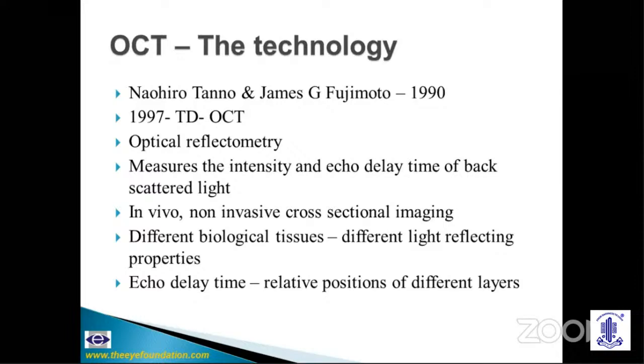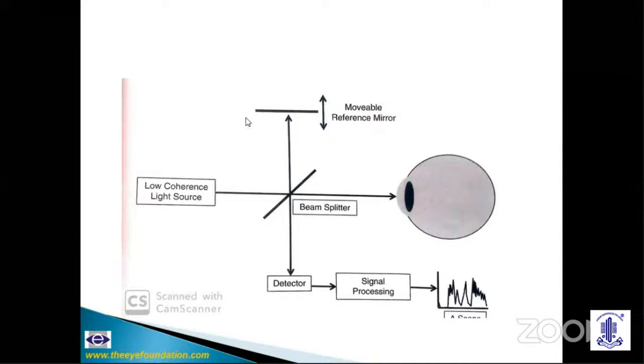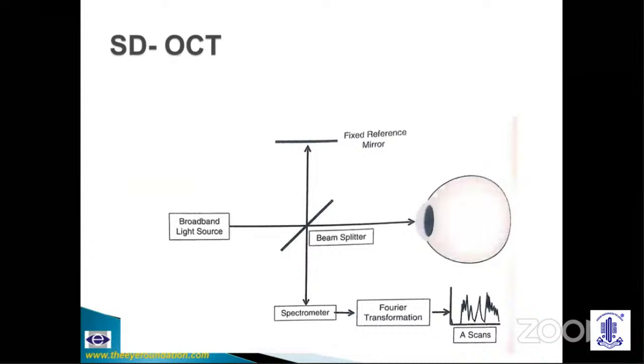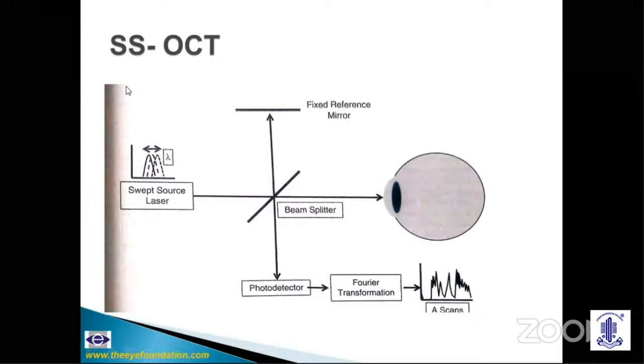The first commercially available OCT was time domain OCT, using a movable reference mirror. Light from a low-coherence superluminescent diode was split by a beam splitter — one beam going to the eye, the other to a movable reference mirror — and interference patterns were used to generate the echo delay time. The movable reference mirror restricted scan speed to 400 A-scans per second. Spectral domain OCT used a fixed reference mirror and a spectrometer to split the wavelength, greatly increasing scan speed to 27,000 A-scans per second. The latest swept source OCT also uses a fixed reference mirror, does away with the spectrometer, and uses a high-speed detector reaching 100,000 A-scans per second.